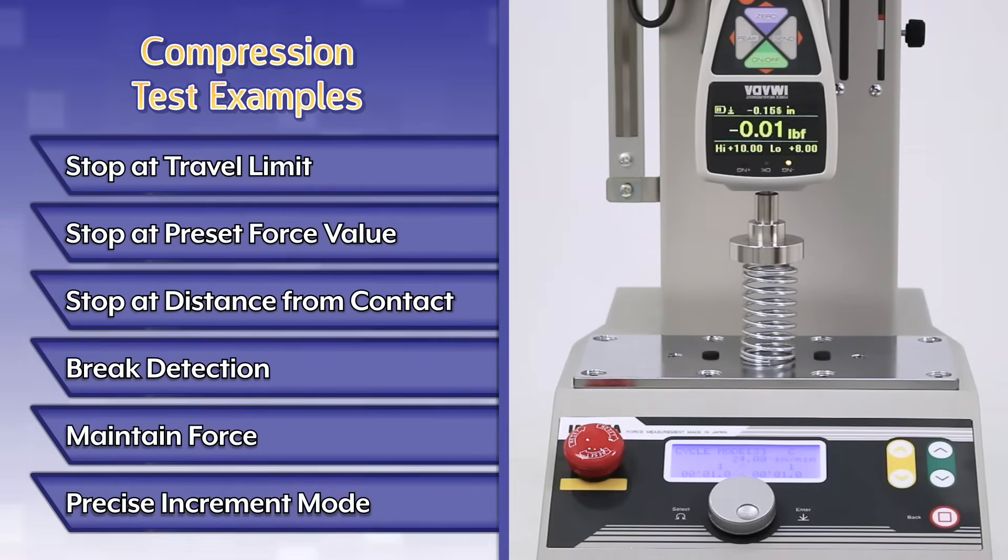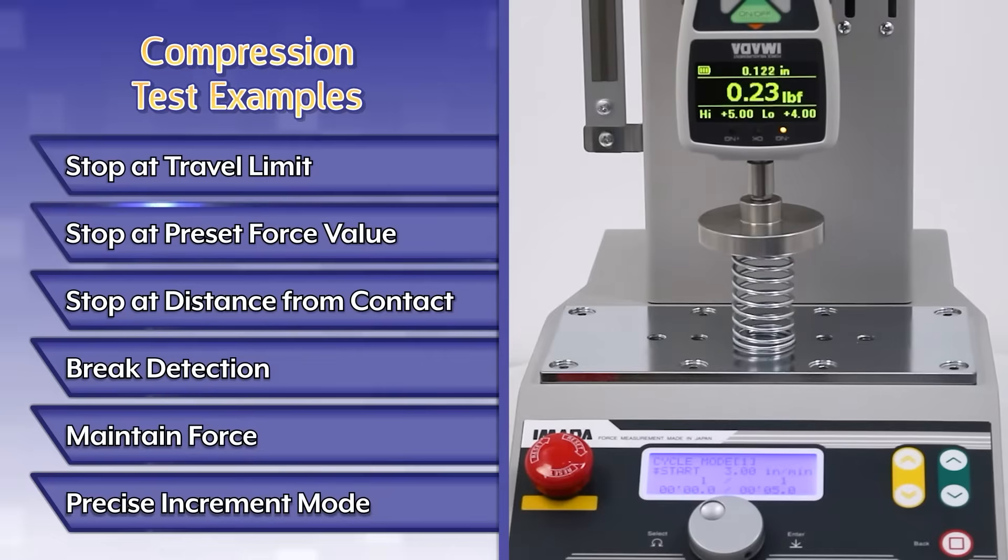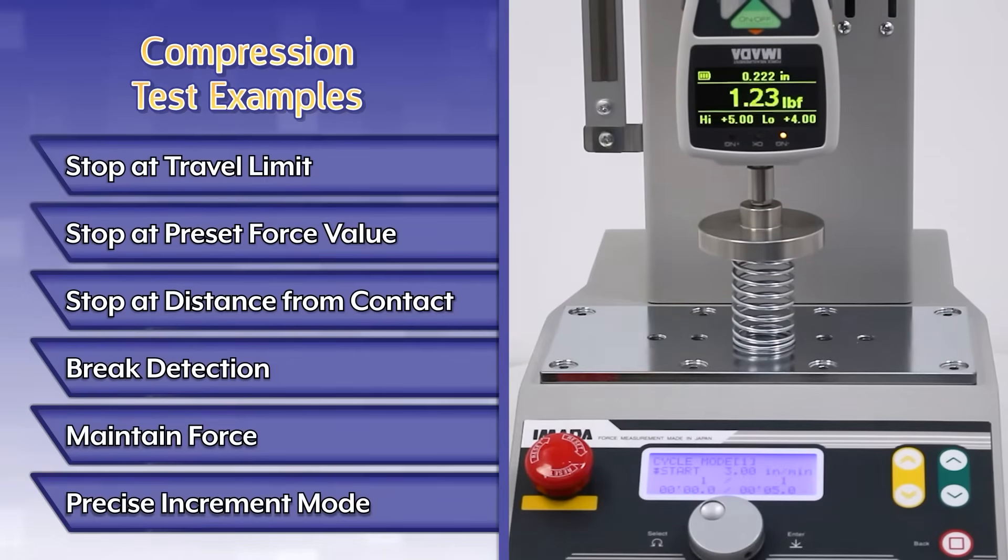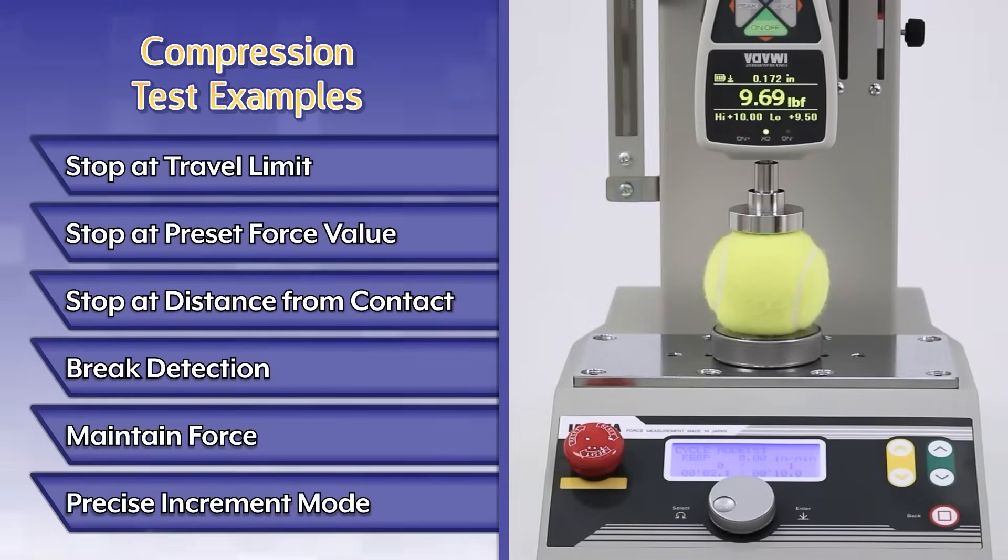These test types include: stop at the travel limit, stop at preset force value, stop at distance from contact point, break detection, maintain force between high-low set points, and precise increment mode.